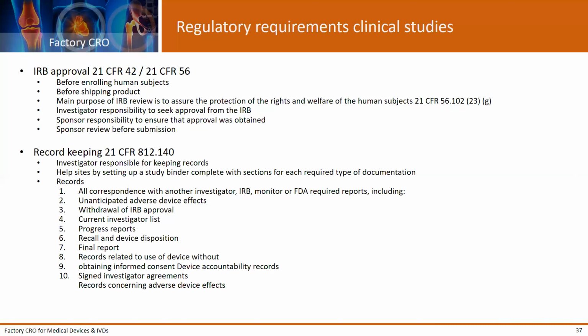The investigator, according to CFR 812.140, is responsible for keeping records, but I do suggest to help the sites by setting up a regulatory binder to file the documents as under 812.140, all the communication, all adverse events, IRB communication, progress reports, and agreements.